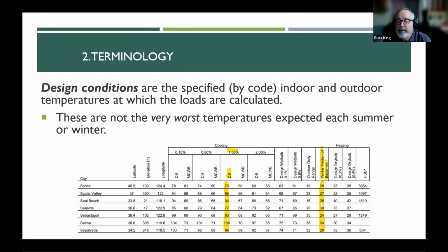All right, so we use a number called the 1 percentile day, and in Sebastopol, it's 95 degrees, okay? Does that seem hot or cool to you? Anyone live in Sebastopol? Does it get above 95 degrees very often in Sebastopol? And you might say, gosh, yeah, a few days ago, it hit quite a bit warmer than that. But that's the peak temperature of the day. Now, let's say the other day hit 98. It wasn't 98 all day. It was only 98 for a very short period of time.